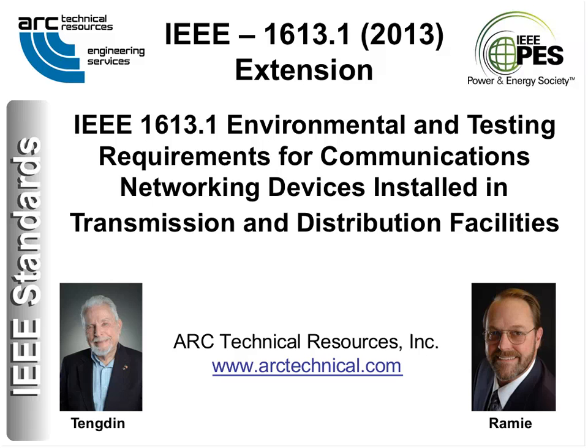What we did is we followed Europe's lead, and we followed the American manufacturers who were selling into Europe's lead, like that Cisco and SEL ads that I showed you earlier. Said they were doing these documents, said they were hitting these levels in European Union. There's no reason that American products should be worse. And so we were ordered by the NIST SGIP to integrate or harmonize what was required in the IEC with what the IEEE pair of documents would require.